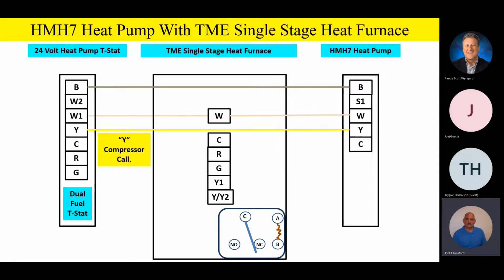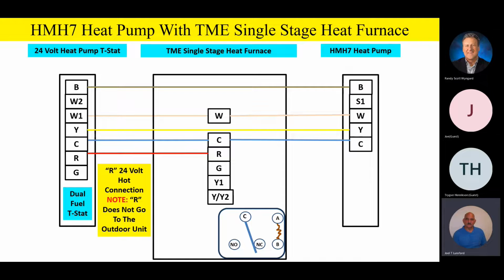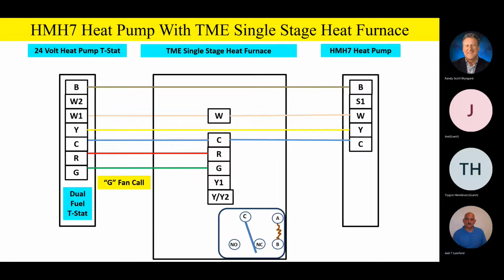Now, just like we had before with our air handlers, that Y is our compressor call that goes outside to the outdoor unit from the thermostat. C is 24-volt common, just like we had before. You'll notice it looks a lot like our air handler, and it is. It's just that we have hard screw terminals on the indoor product, and we may have a little different terminal configuration than we had with our air handler, but it's essentially the same type of wiring schematic. R is 24-volt hot, and please remember, team, that goes strictly from the indoor unit to the heat pump thermostat. It does not go outside. R does not go outside. G is still our 24-volt signal for fan operation, like we had before. G is our 24-volt call for fan operation from the thermostat.